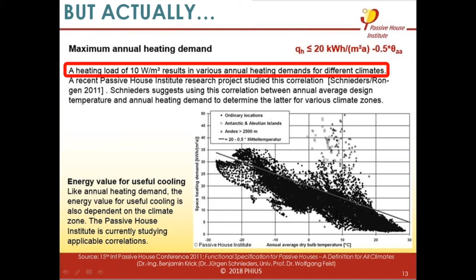The problem here is that I believe what the PHI, because of lack of experience really, did not realize is that 10 watts per square meter per year is almost impossible to meet for smaller structures in climates that have very big delta T's. So for my home, for example, I thought Urbana, Illinois was pretty similar to Germany. Well, absolutely not. It gets super cold in the winter and super hot in the summer. And to meet the 10 watts per square meter, or 1 watt per square foot, peak load requirement, I would have needed a 200 R roof, 160 in the walls, 20 R in the windows, and like a 100 under the slab. And arguably that is no longer cost effective or reasonable, or it is just not possible.